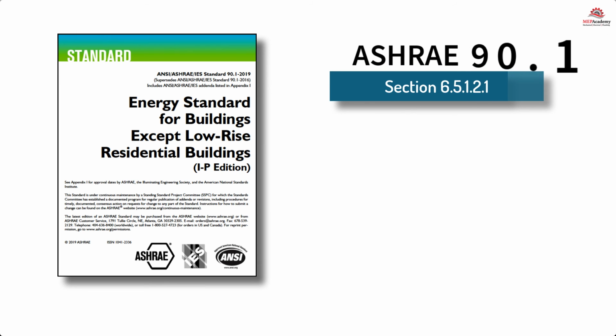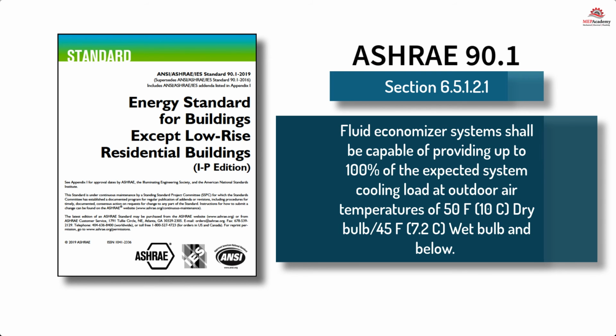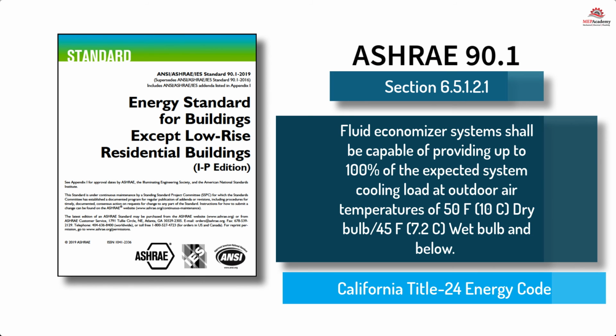ASHRAE 90.1, 2019, section 6.5.1.2.1. If your local building code has adopted ASHRAE 90.1, then the use of a waterside economizer could be mandated by code under certain conditions or as one of several options to achieve energy-saving goals. When the temperature drops below a set value, such as 50 degrees Fahrenheit dry bulb, 45 degrees wet bulb, or 10 degrees Celsius dry bulb, 7.2 degrees Celsius wet bulb, mechanical cooling would shut down and 100% full waterside economizer would be active. For those that live in the state of California in the United States, the temperature requirement thresholds are the same as mandated in the Title 24 Energy Code.